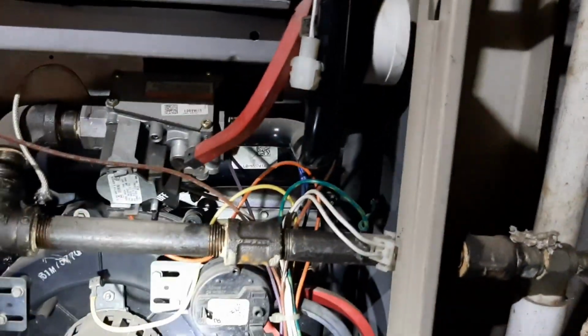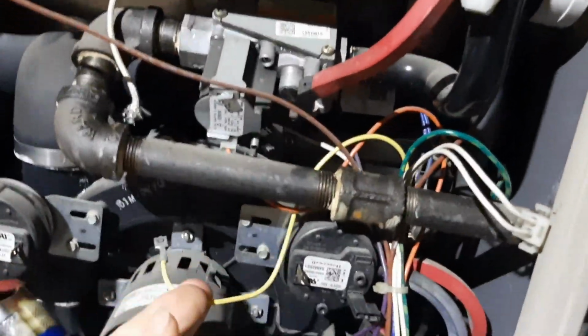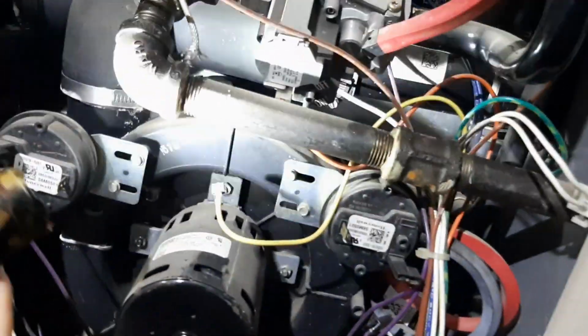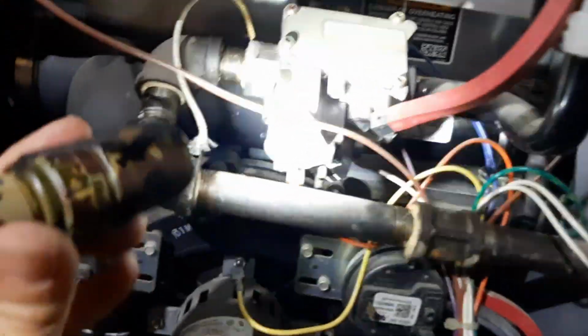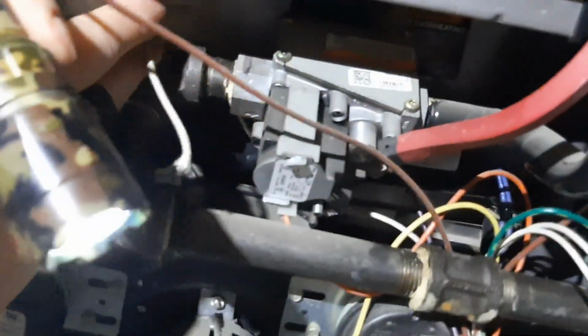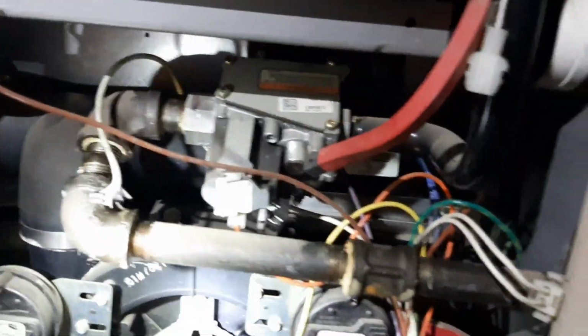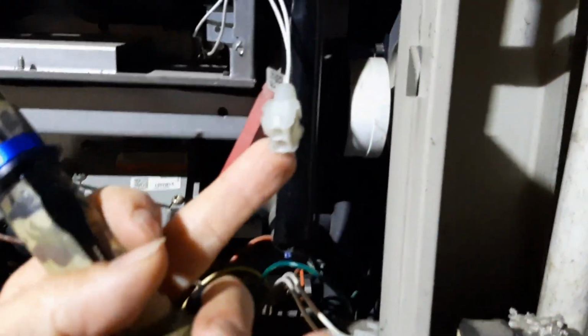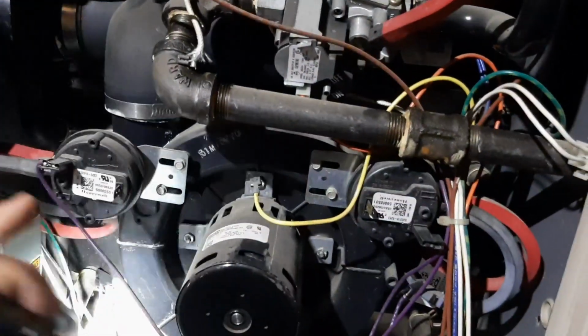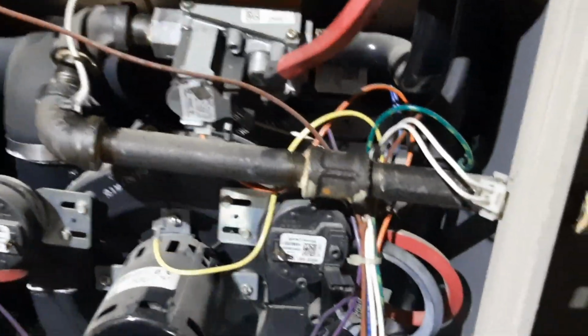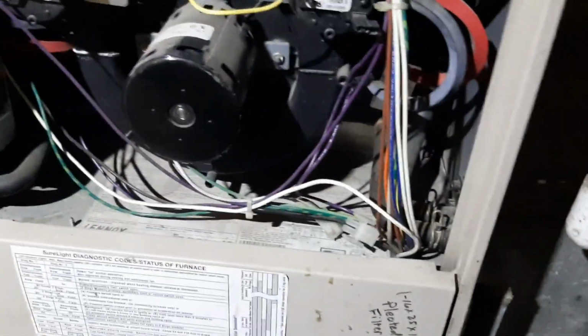I've got a wire pulled - somebody's disabled a wire pulled from the gas valve. I got a wire hanging there. The igniter's been unplugged, pressure switch unplugged, so obviously somebody disabled the heat on this thing. And my blower, I turned off. Let's get in here and see why it's running.